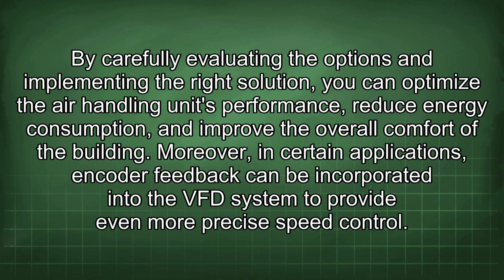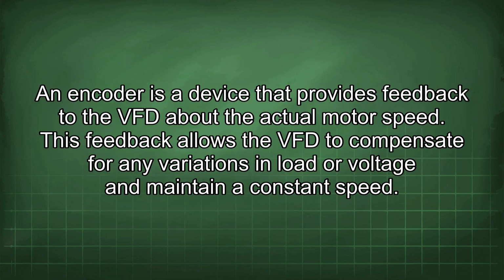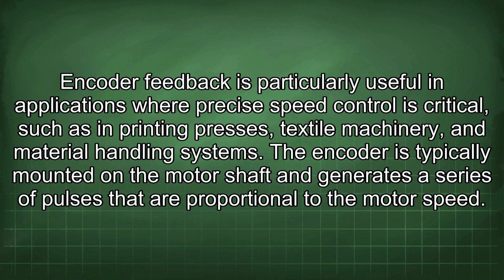Moreover, in certain applications, encoder feedback can be incorporated into the VFD system to provide even more precise speed control. An encoder is a device that provides feedback to the VFD about the actual motor speed. This feedback allows the VFD to compensate for any variations in load or voltage to maintain a constant speed. Encoder feedback is particularly useful in applications where precise speed control is critical, such as in printing presses, textile machinery, and material handling systems.